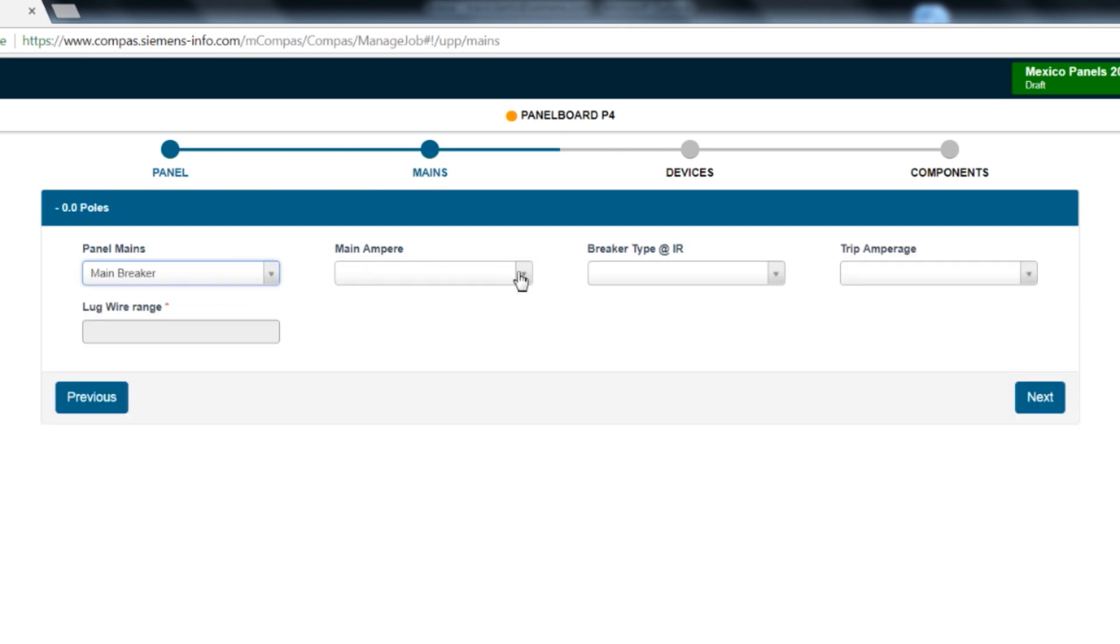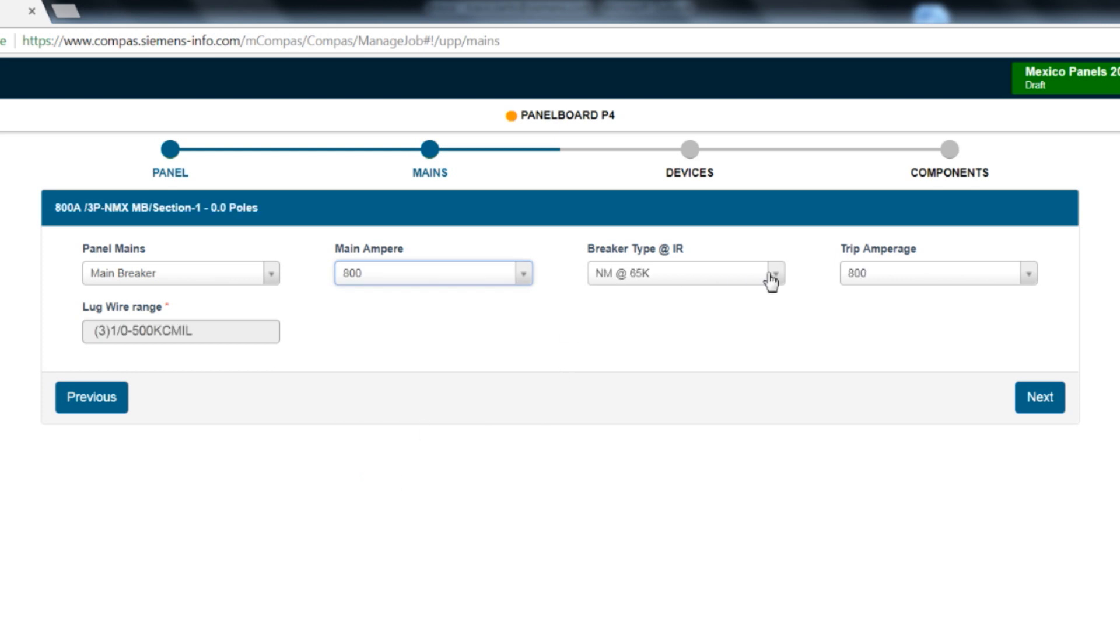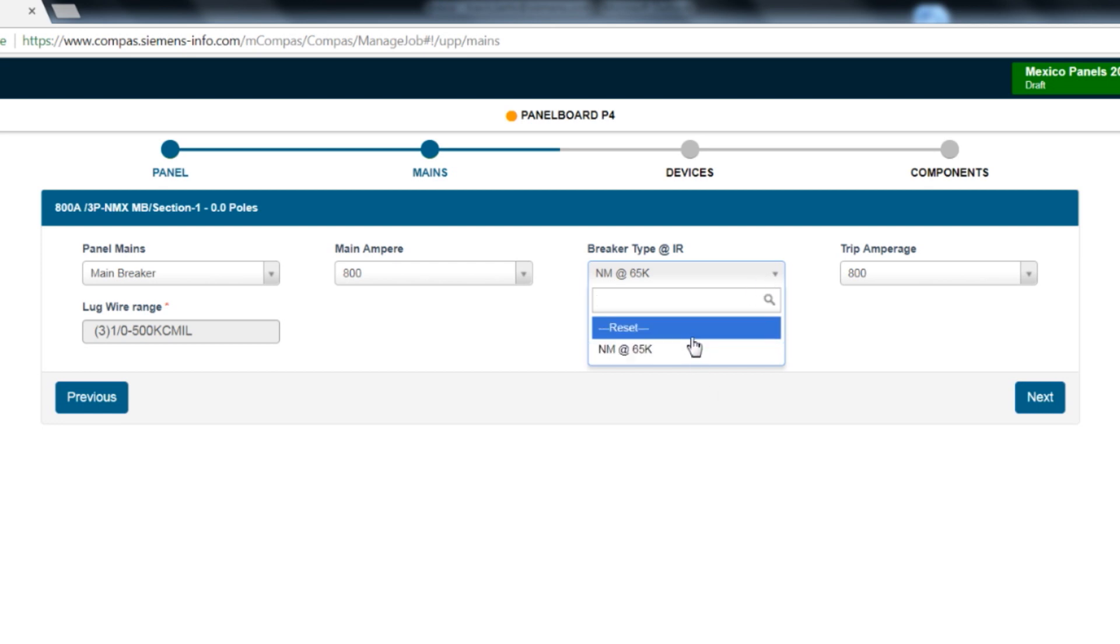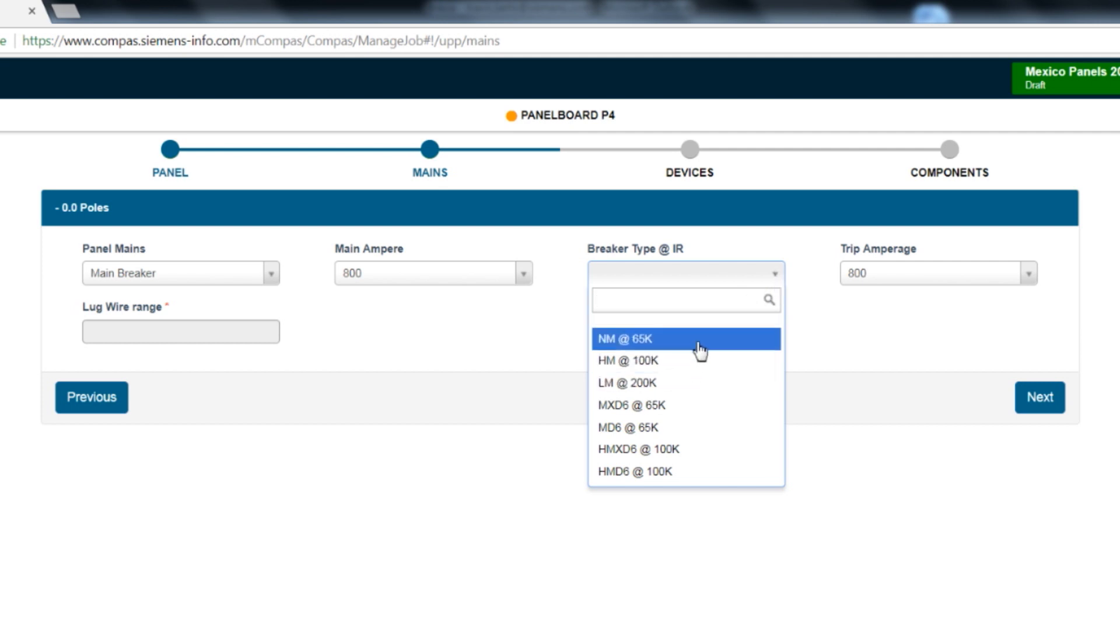For the main breaker, you will be able to select anywhere from a 400 amp to an 800 amp frame. Select the appropriate main breaker amperage on this dropdown. The next selection is for the actual main breaker. COMPAS Go will select the most cost efficient breaker for the application as default. If you would like to select a different main breaker, you can hit reset and it will show all main breaker options available. This will also allow you to match the main breaker with a circuit breaker you may have in stock.